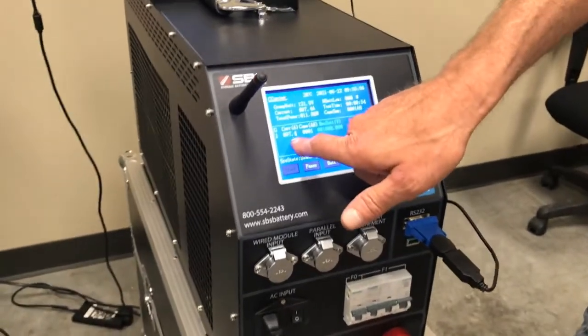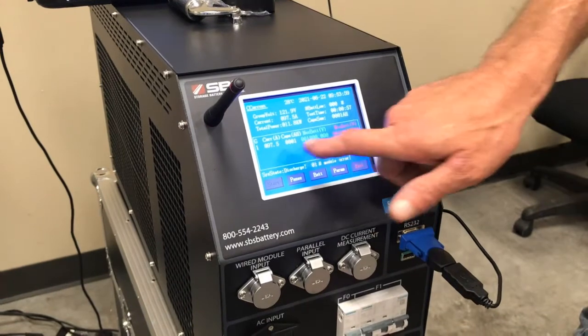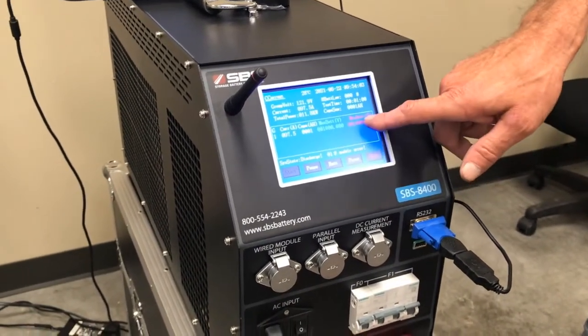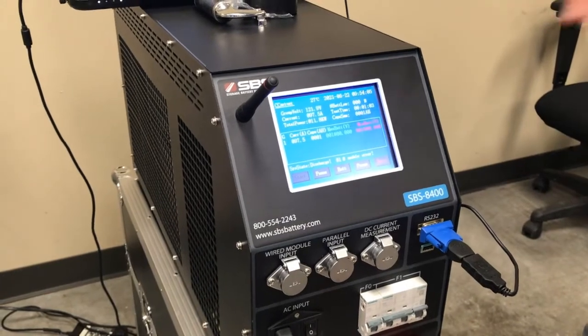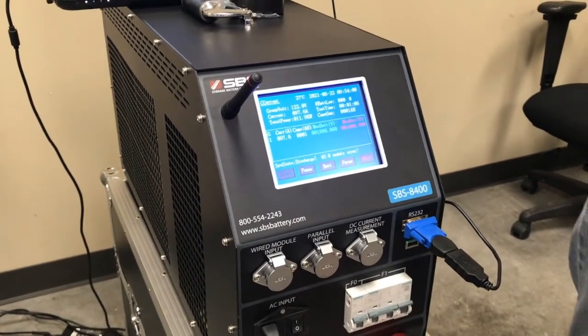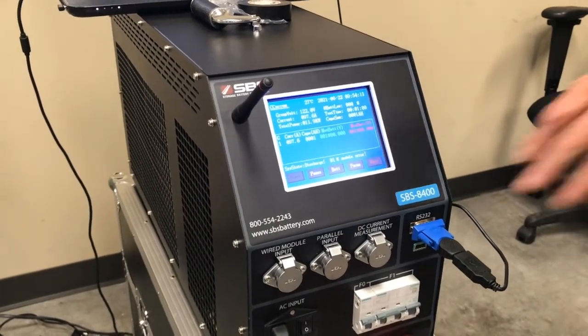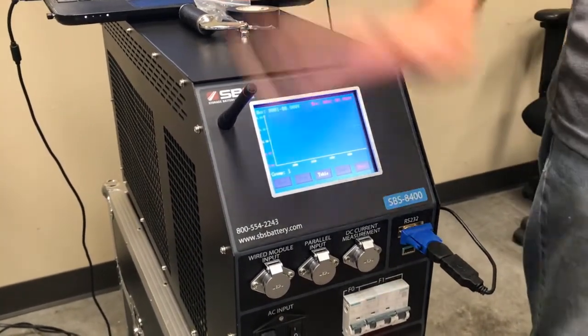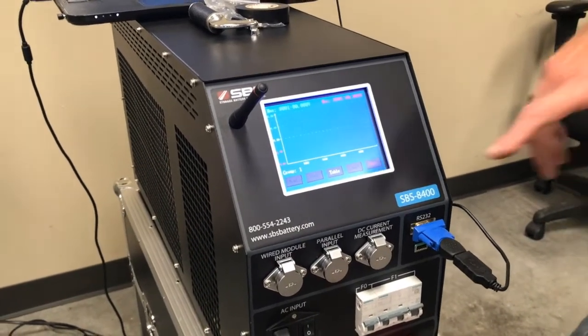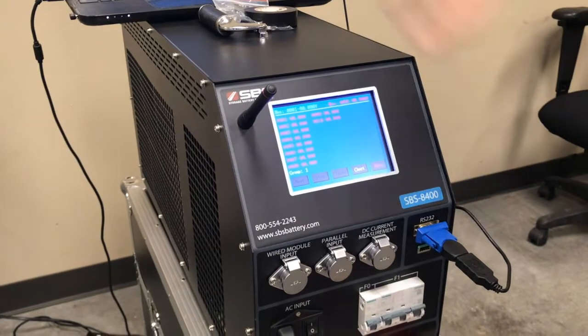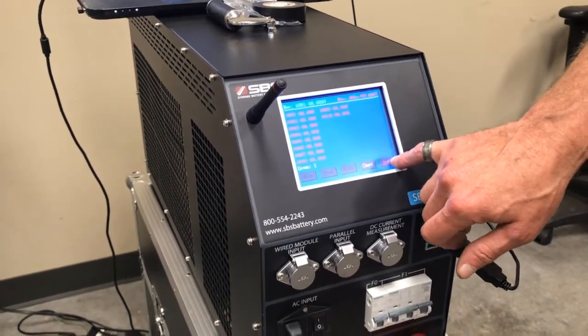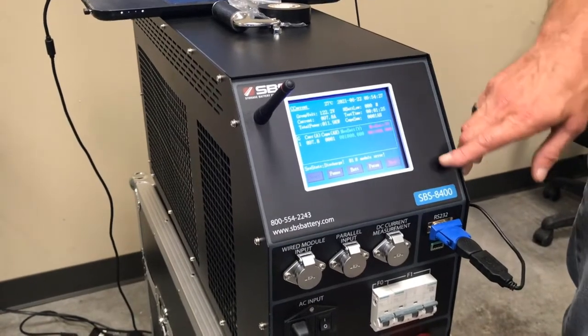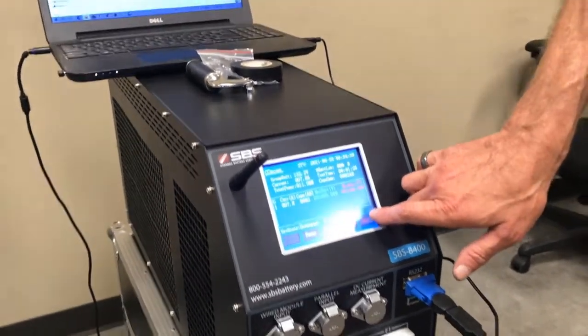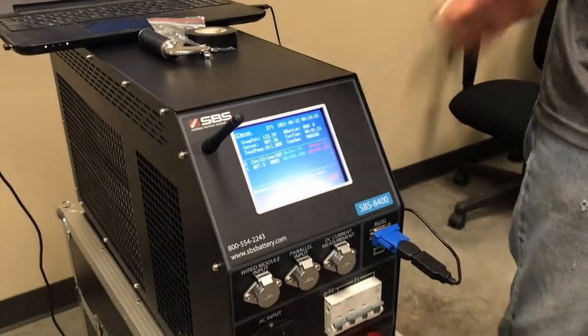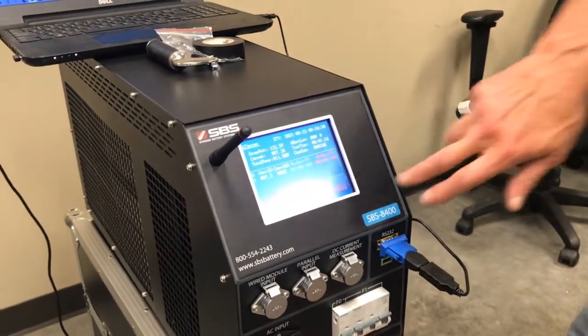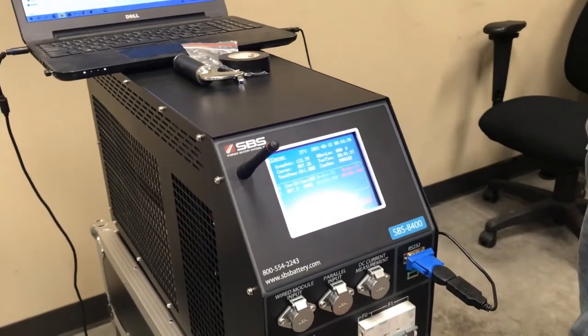On the display, I'm going to see my current. I'm going to see my amp hours removed. I'm going to see my highest voltage and my lowest voltage, green and red, so that I can walk by the machine and at a glance get an idea of what the condition of the cells are. I can press the battery key and I can go in and look at those individual values as the test is running. I can go back to table view, view them all on the table. Hitting the exit key there takes me back to the main screen or the discharge screen. Hitting the exit key here stops the test. Okay. So in an emergency, I can stop the test simply by pressing the exit button.